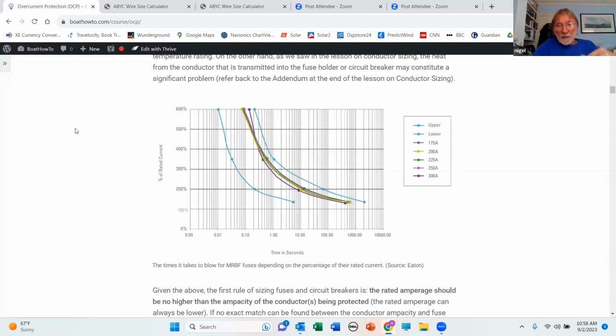So then the amp rating of the fuse itself is going to be dependent on the size of the conductor that comes off that battery. If it's a 2-aught conductor and it's not bundled or anything, it could be as high as 330 amps. If it's a 4-aught conductor, it could be 400 and something amps. So the actual amp rating is determined by the conductor. The AIC rating is just given by the fact that it's a Class T fuse. So all those Class T fuses, irrespective of what amperage, have an AIC rating of at least 20,000 amps.